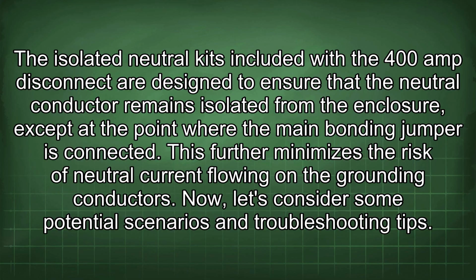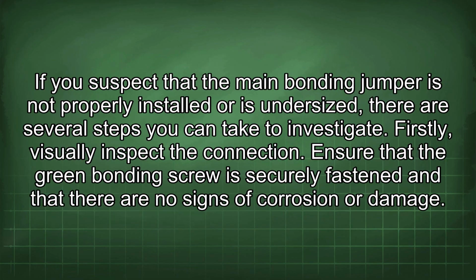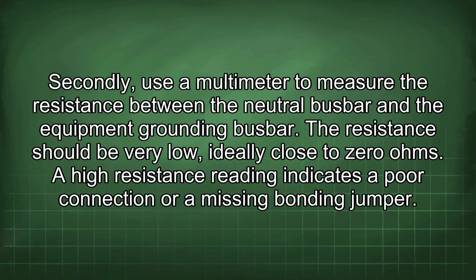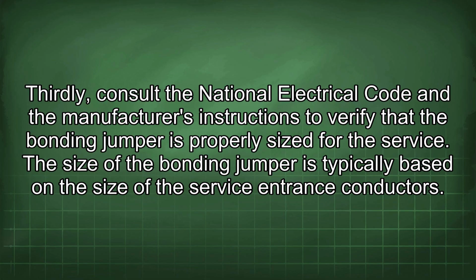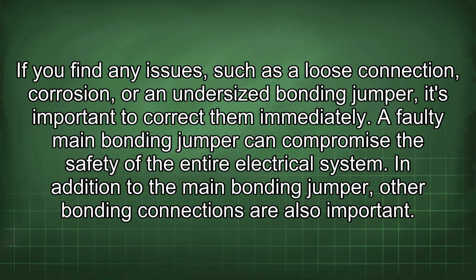Now, let's consider some potential scenarios and troubleshooting tips. If you suspect that the main bonding jumper is not properly installed or is undersized, there are several steps you can take to investigate. Firstly, visually inspect the connection. Ensure that the green bonding screw is securely fastened and that there are no signs of corrosion or damage. Secondly, use a multimeter to measure the resistance between the neutral busbar and the equipment grounding busbar. The resistance should be very low, ideally close to 0 ohms. A high resistance reading indicates a poor connection or a missing bonding jumper. Thirdly, consult the National Electrical Code and the manufacturer's instructions to verify that the bonding jumper is properly sized for the service. The size of the bonding jumper is typically based on the size of the service entrance conductors. If you find any issues, such as a loose connection, corrosion, or an undersized bonding jumper, it's important to correct them immediately. A faulty main bonding jumper can compromise the safety of the entire electrical system.